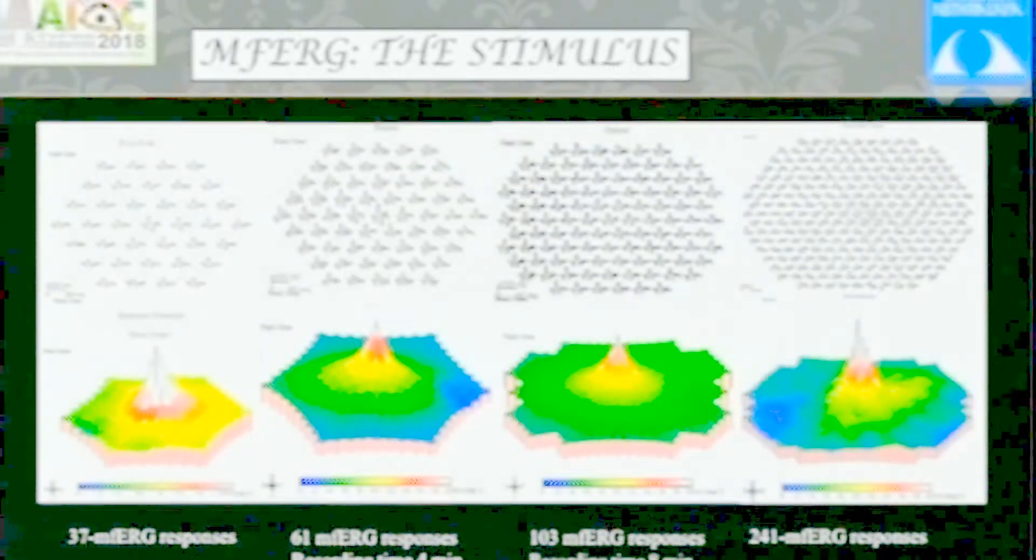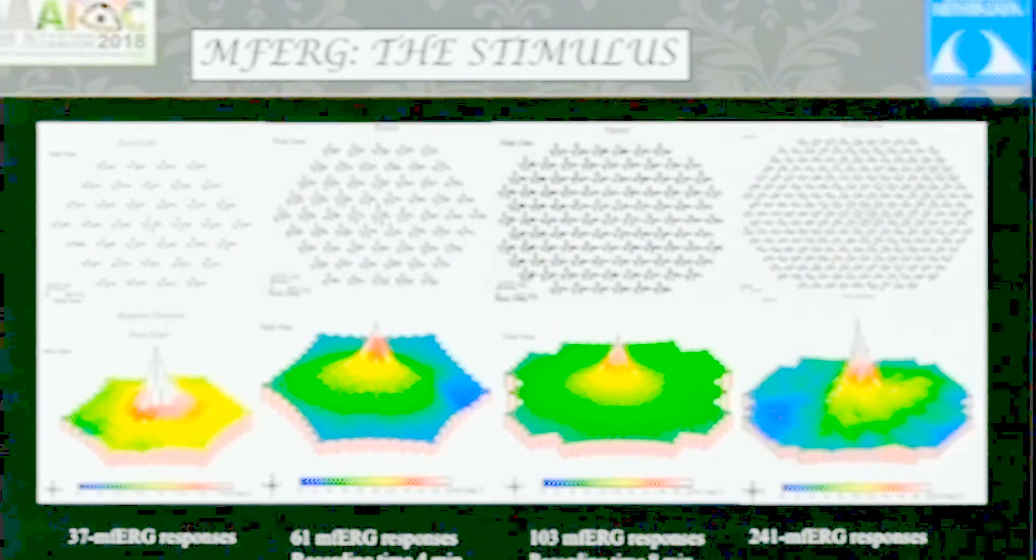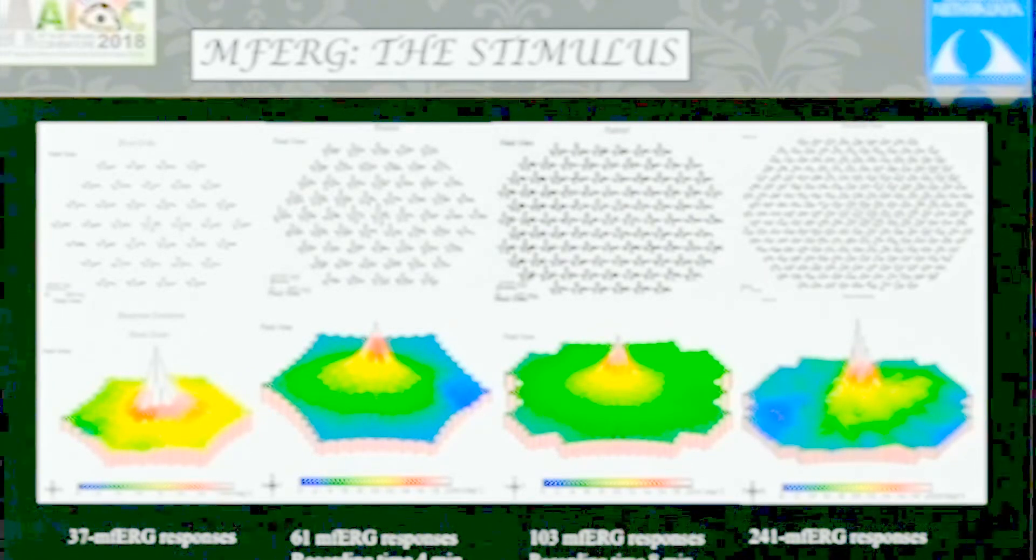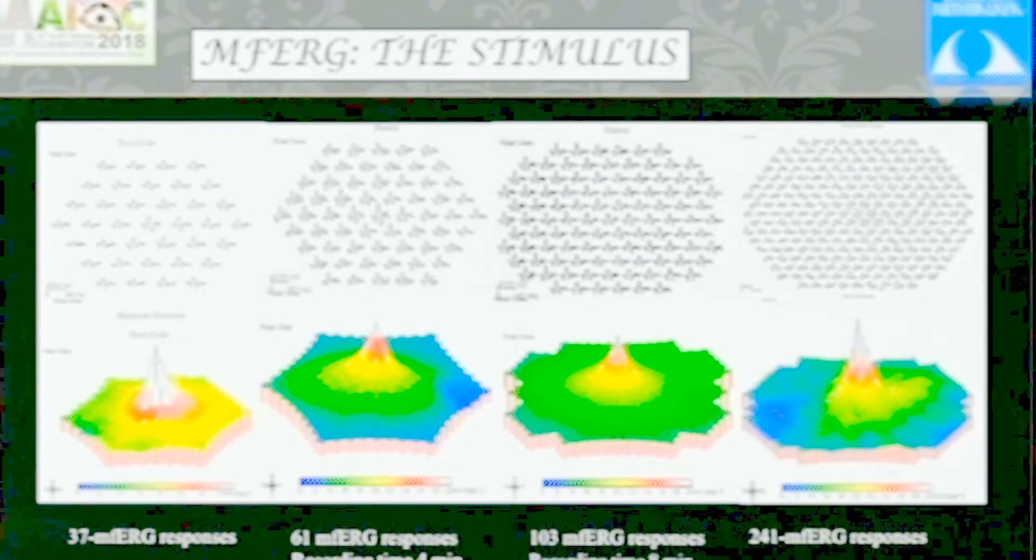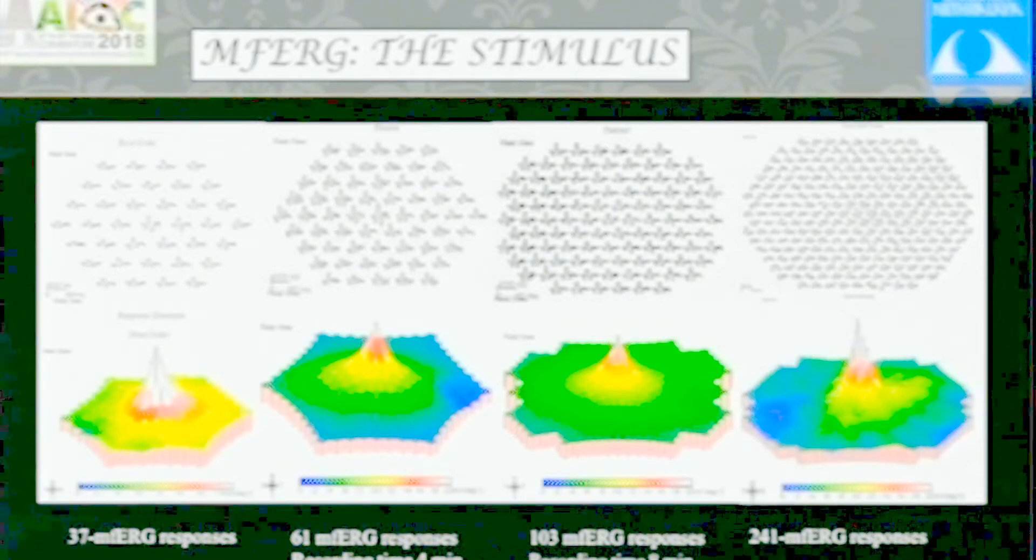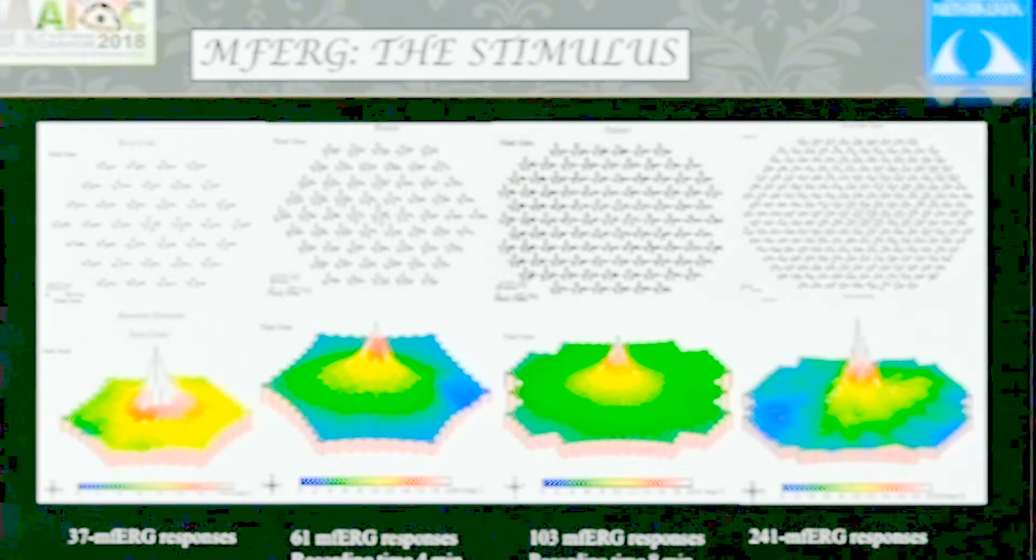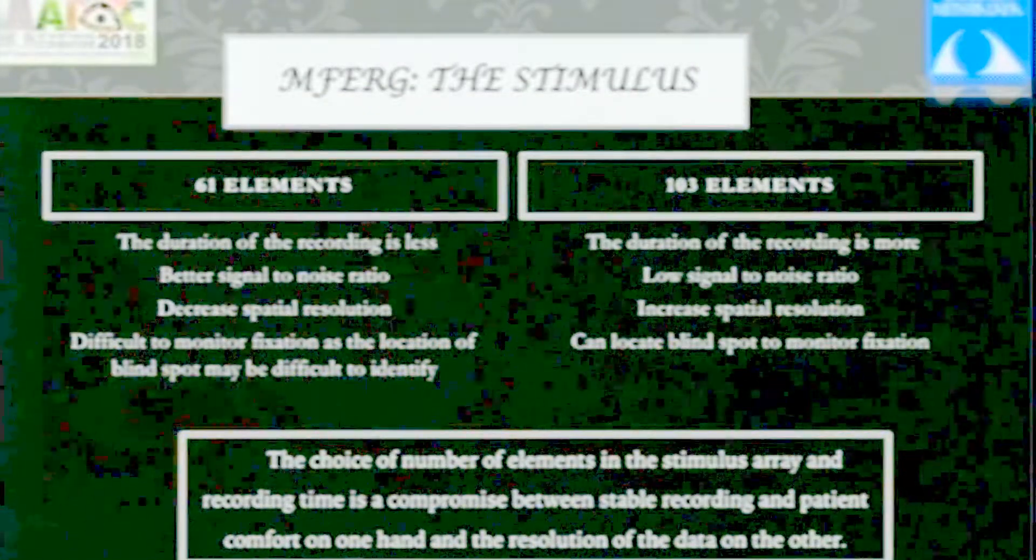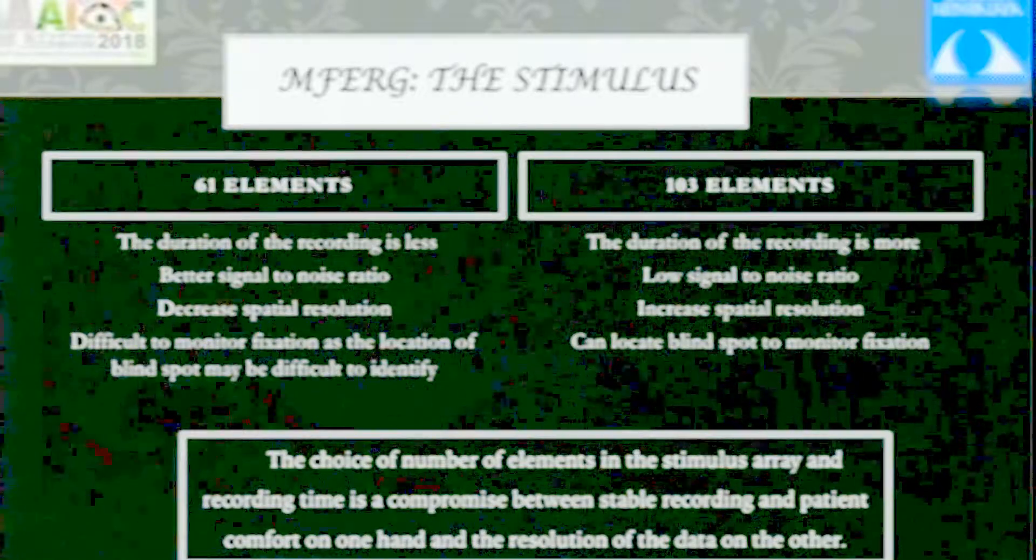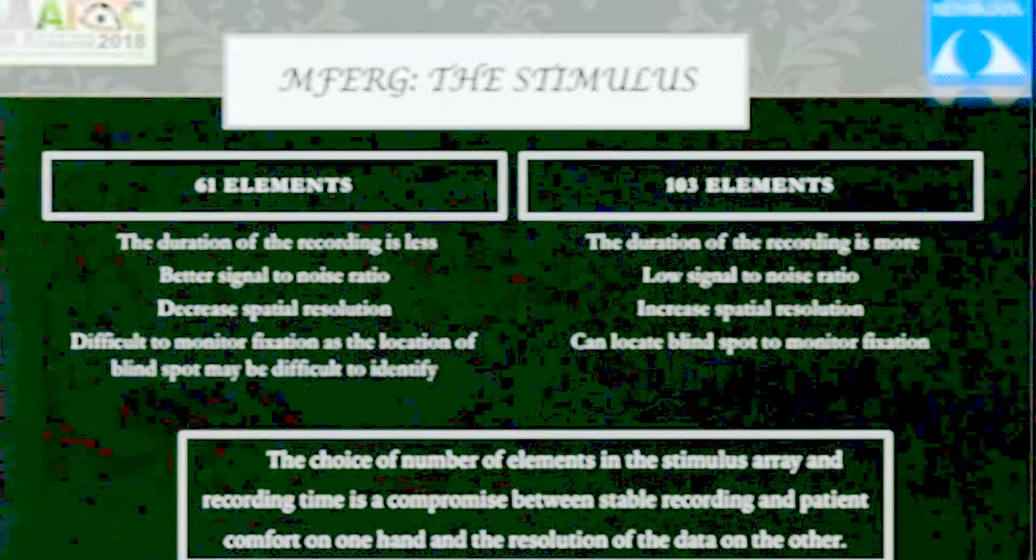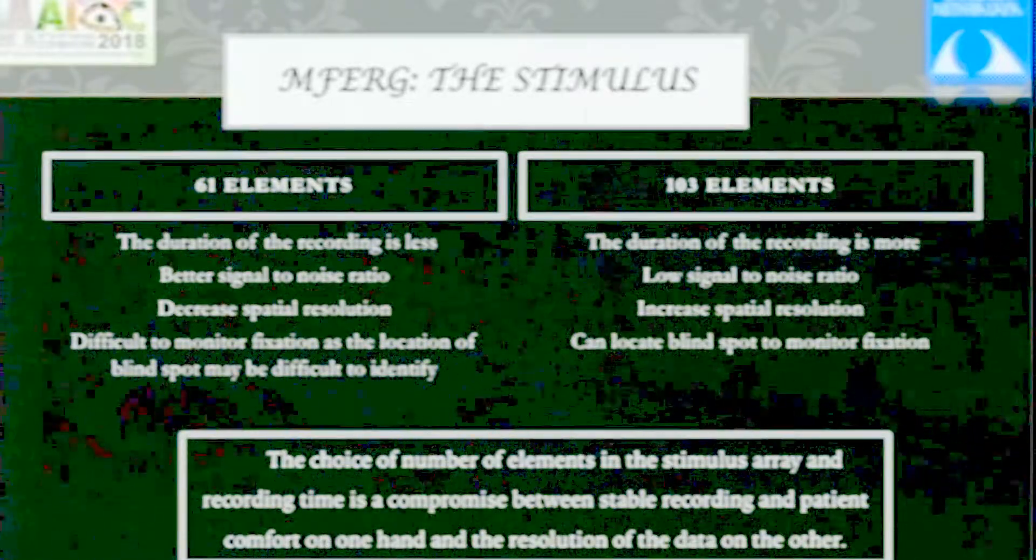This shows the trace arrays you can measure. The first has about 37 hexagons, the second 61, the third 103, and the fourth 241. As the number of hexagons increases, the difficulty level and recording time become very high, and patient cooperation becomes low. The ISCEV standards recognize 61 elements and 103. The choice is limited by a trade-off between better signal-to-noise ratio for 61 elements and better spatial resolution where you can identify minute defects in 103 element stimulus.